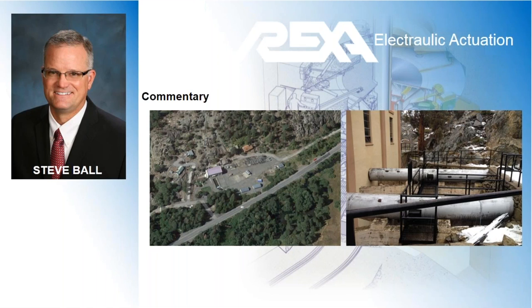It didn't have a deflector. It didn't have a stream bender. It wasn't articulated at the nozzle body. The main power needle was directly at the impulse turbine, and then below it there was a relief needle that was aimed at an energy absorber on the far side of the turbine pit. They were mechanically linked, so when the turbine, let's say, was to trip, to remove water from the turbine, as the main power needle was going closed, the mechanical linkage to the auxiliary needle would pull it open to relieve or to protect the penstock from water hammer. So it would send the flow below the turbine.